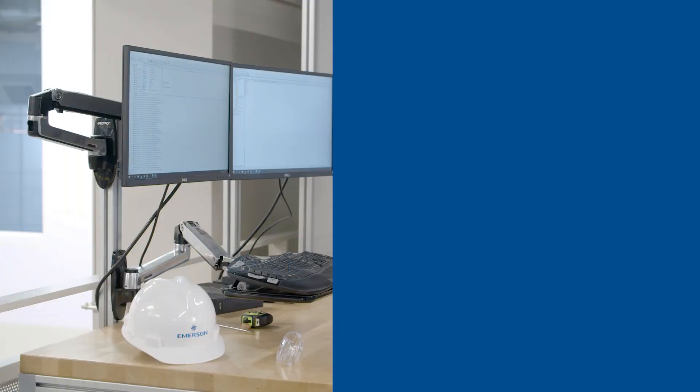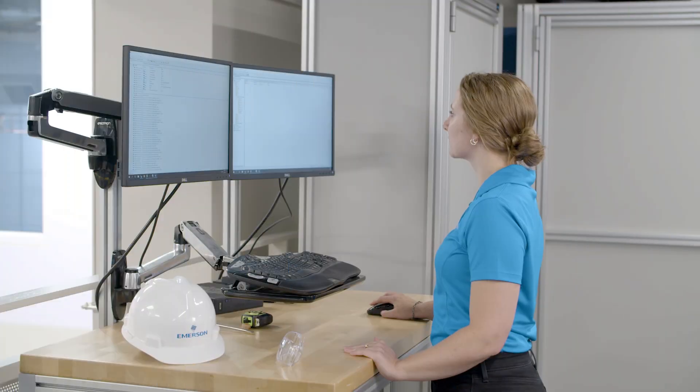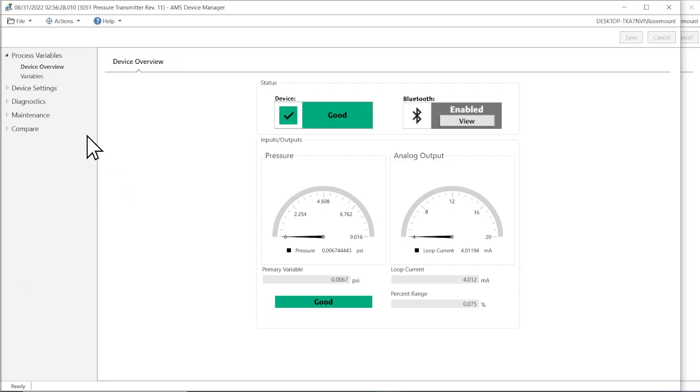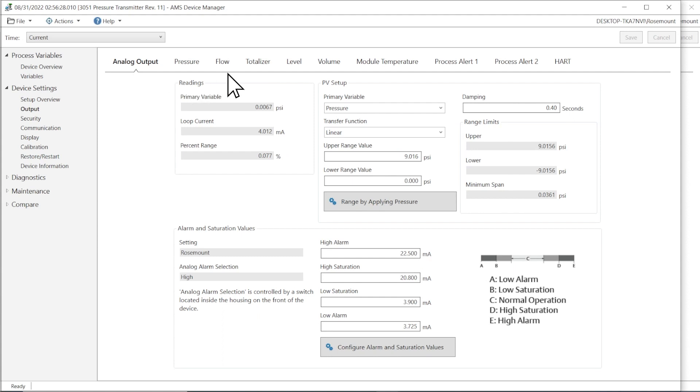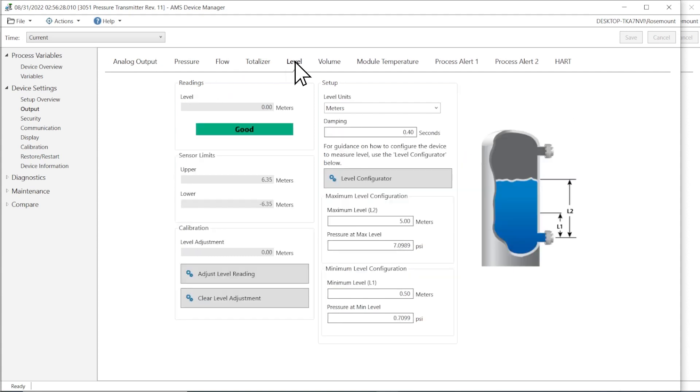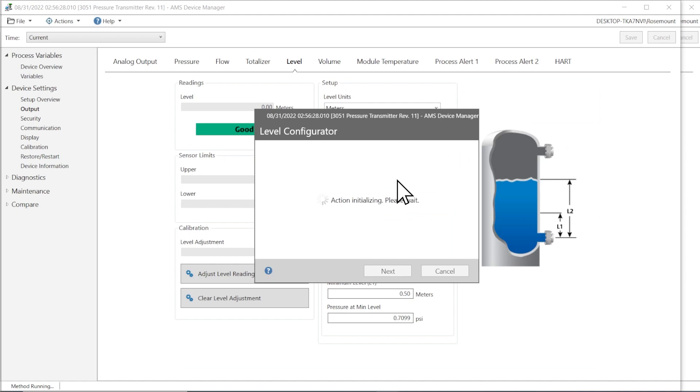Once connected to the transmitter, navigate to the Device Settings menu, select Output, then Level. Start the Level Configurator method. Read and acknowledge the warning message.